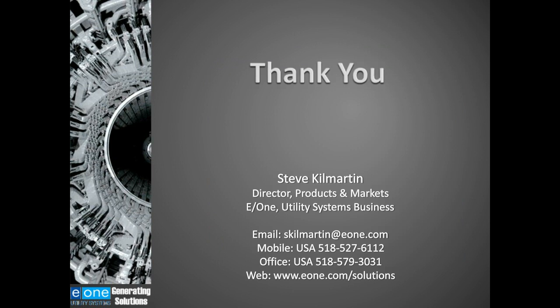In summary, both units, the GCMX and the GCMA, use detectors that are very effective in detecting submicron particles that are created by overheated materials, such as insulation. Both are well suited for the applications that they are being used in, and both can help ensure reliable operation of hydrogen and air-cooled generators, helping to minimize the chances of a catastrophic generator failure. Thank you.